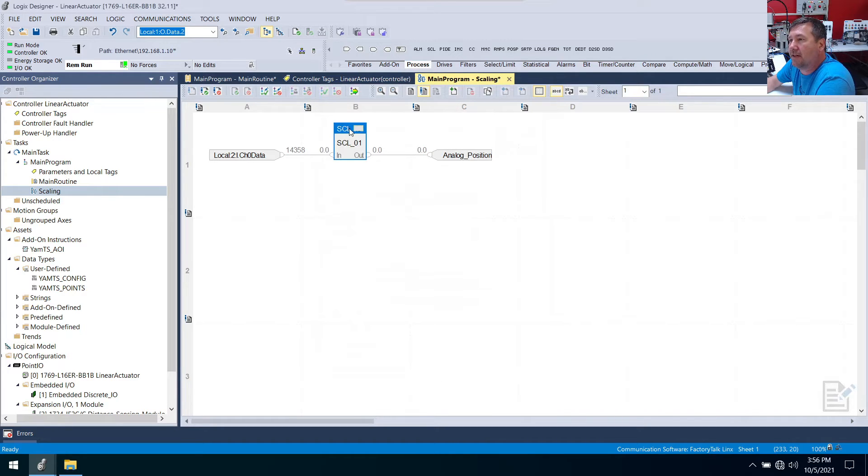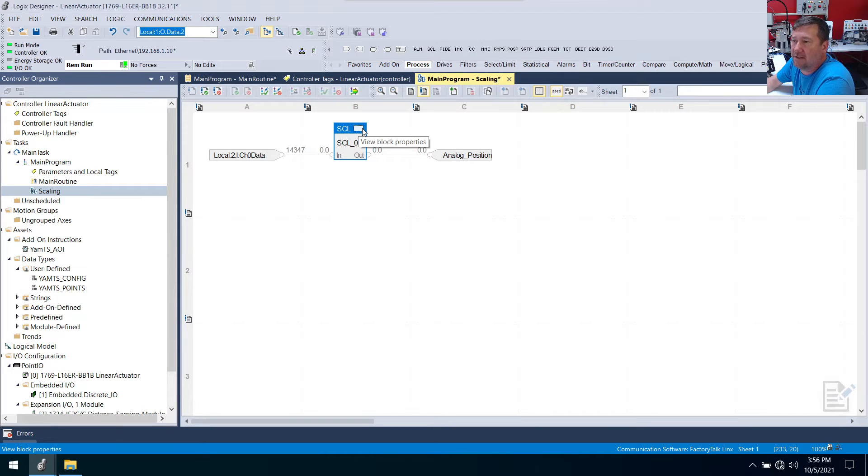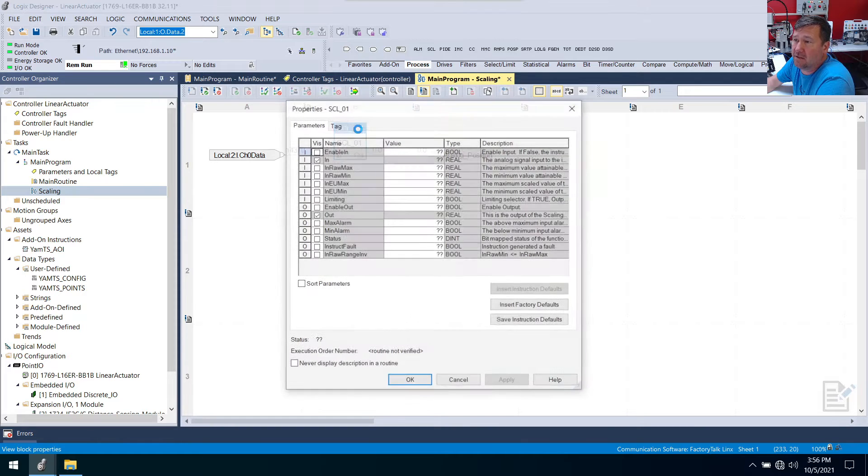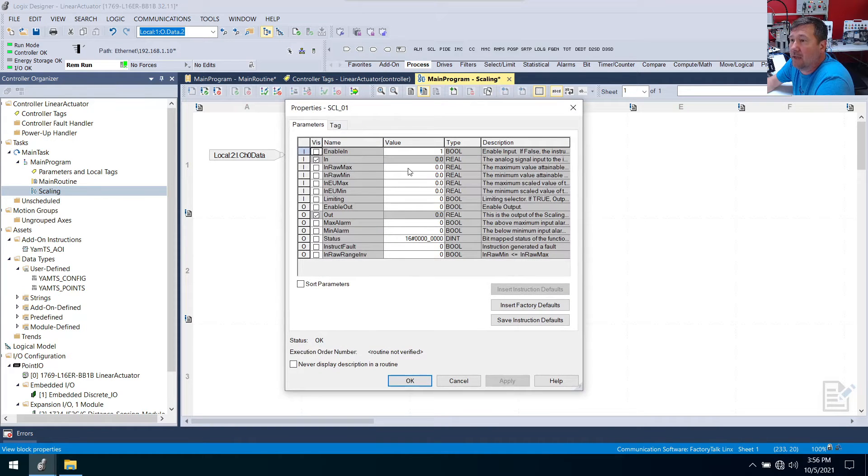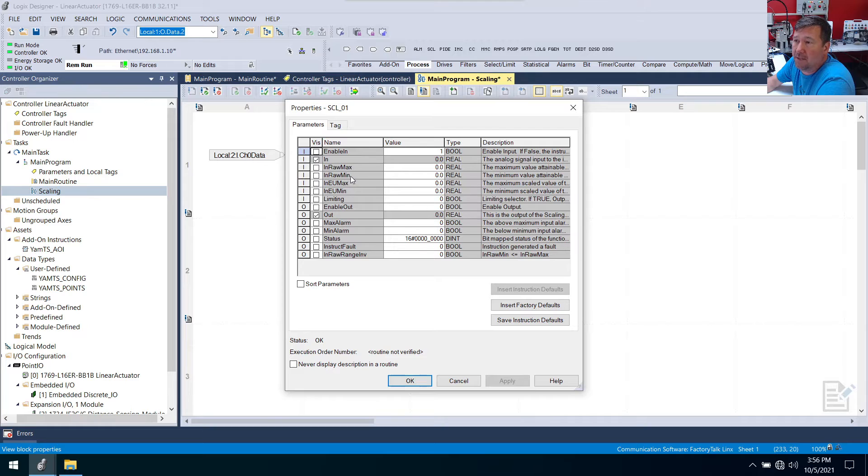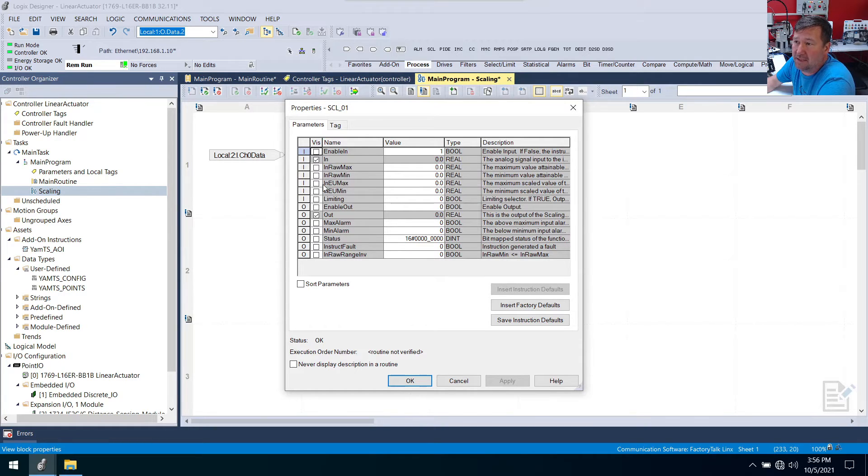And now we need to figure out the SCL values. And so right here at the top right you're going to see there's a little gray box and it says view block properties. We're going to click it. And we're going to want to put in our raw max, raw min, engineering max, and engineering min. And that's what this means here. EU is for engineering units.